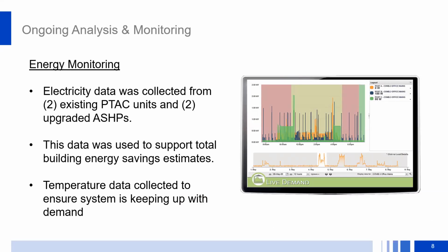So, moving on to the ongoing analysis and energy monitoring. We monitored two of the existing PTAC units and two of our upgraded air source heat pumps so we could directly compare them. This is just a small sample of the building, but it gave us good results to move forward with and look at the total building analysis. Temperature data was kept to make sure that on the coldest and hottest days of the year, the heat pump was keeping up with both heating and cooling.